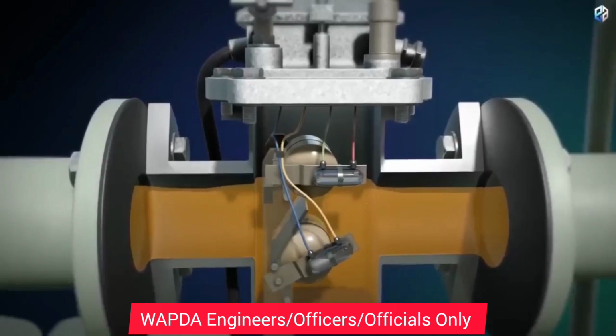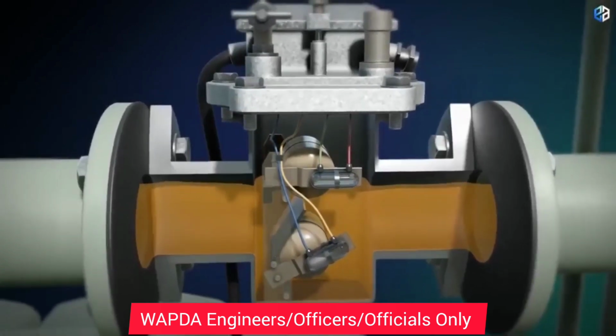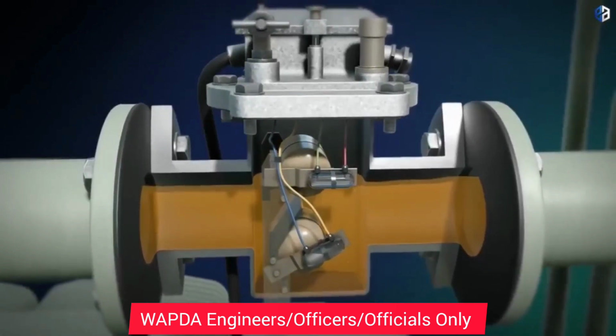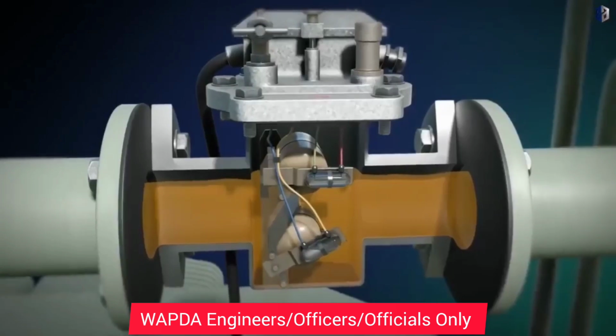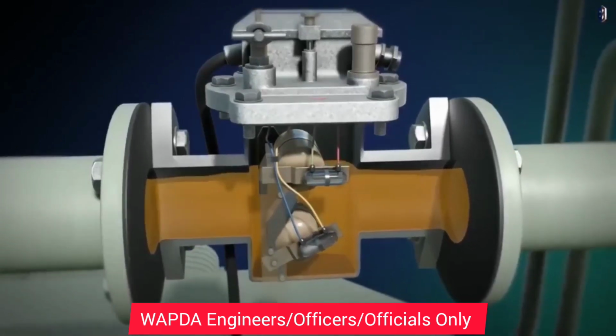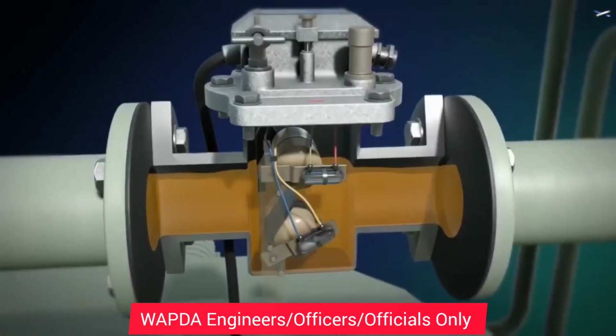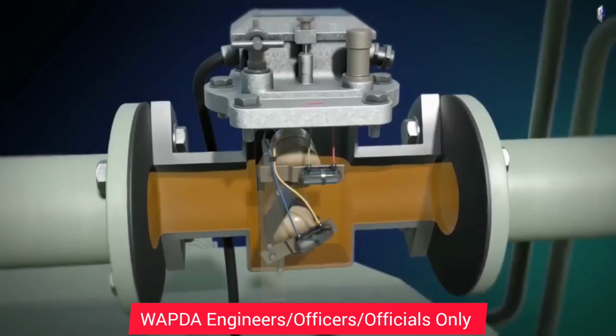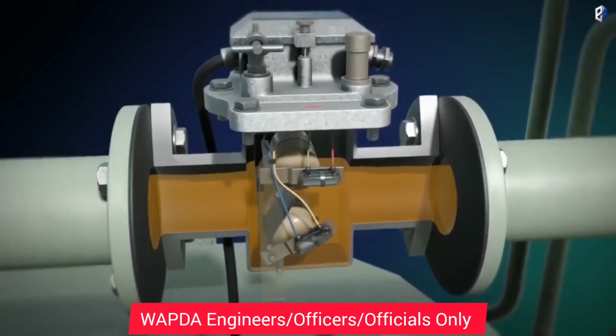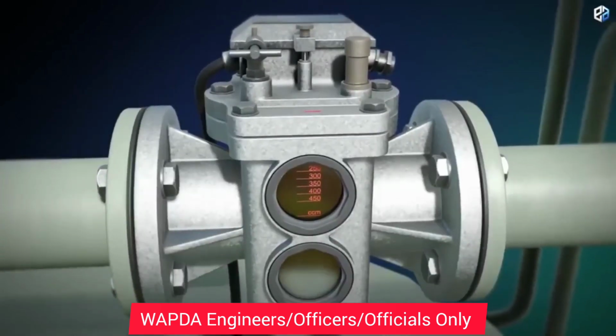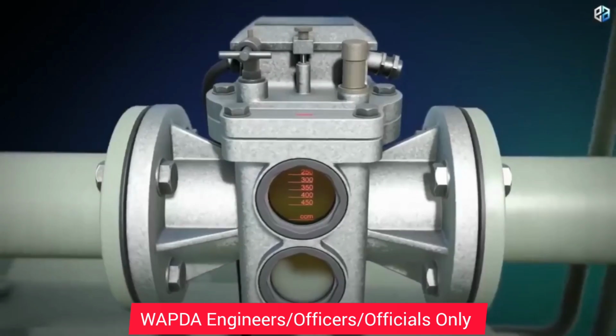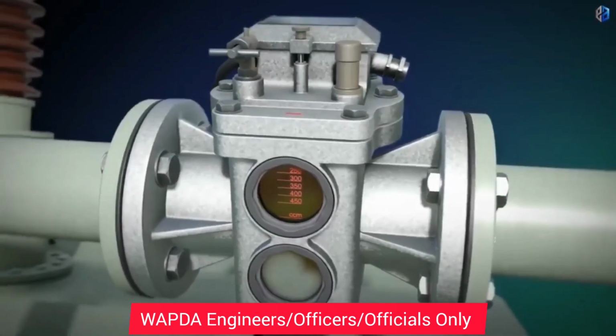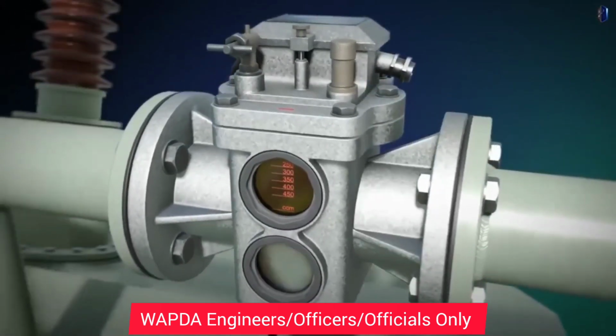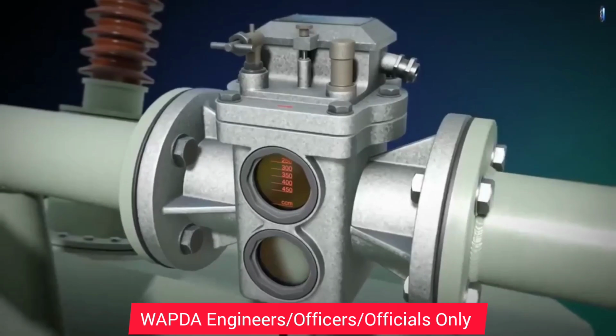As we can see, a Buchholz relay is not able to prevent a transformer fault, but in this case it protects the transformer from particularly severe damage by switching off quickly and reliably. The Buchholz relay works purely mechanically. It does not need an external power supply. This makes it extremely reliable.